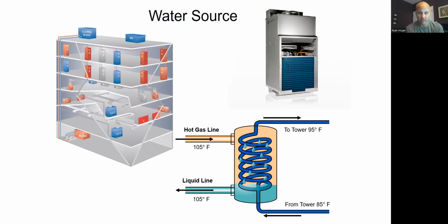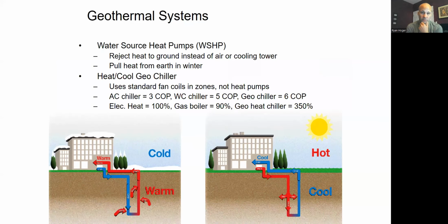So if you're talking about that, yes, you might run into one of those buildings where you're using city water to run it through the coil on the water source heat pump, but you won't be designing one that way. If I read your question again, domestic water sources can be used to the water source heat pump like geothermal. I'm not quite sure what else you could mean. Were you talking about a pump and dump system, Clark? Or were you talking about something over here? And instead of having this, you want to use...